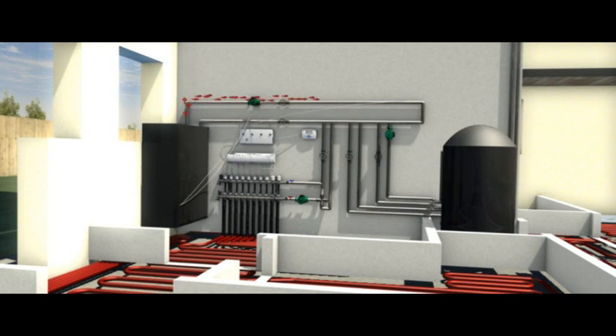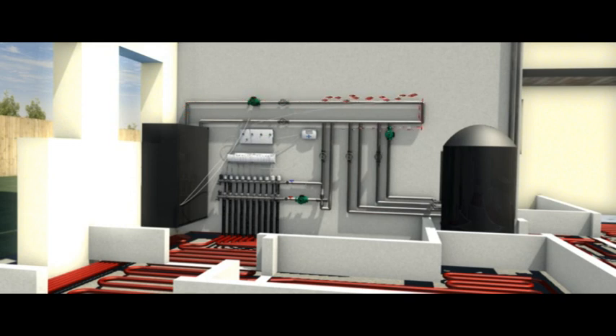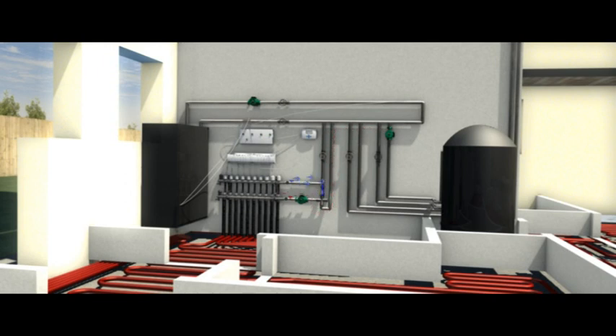Hot water will then flow through the primary and secondary pipework into the underfloor manifold. The water temperature is regulated by mixing hot water from the boiler with cooler water returned from the underfloor circuits through a three-port mixing valve.